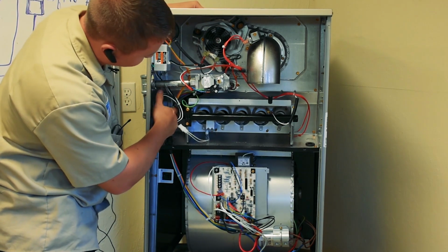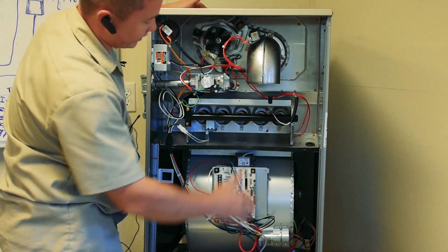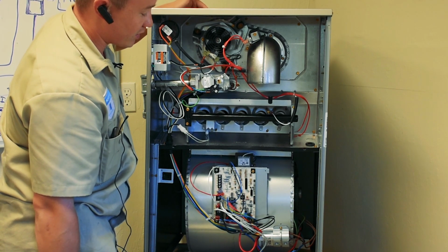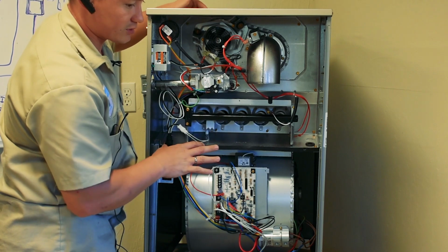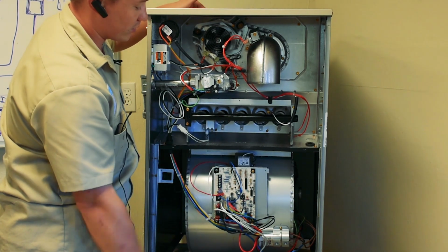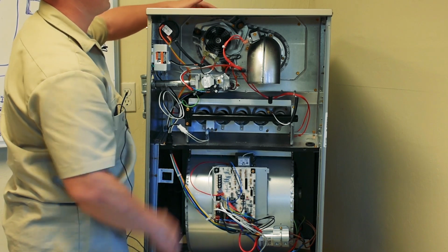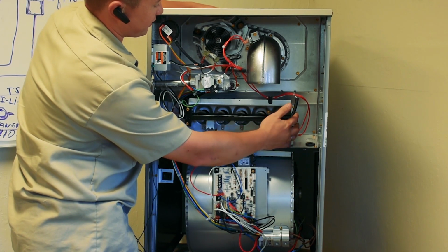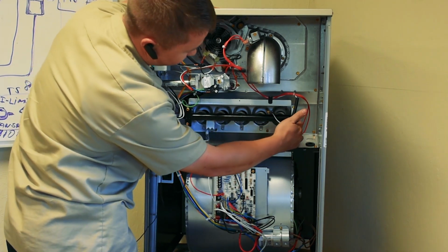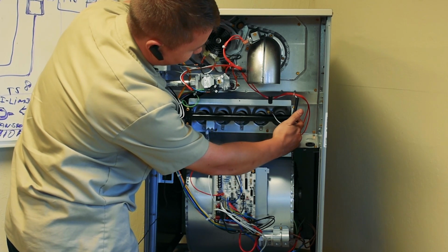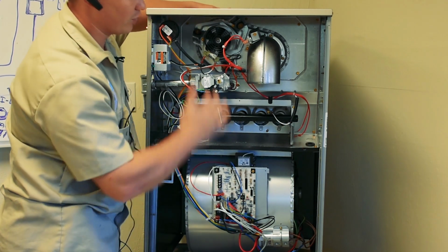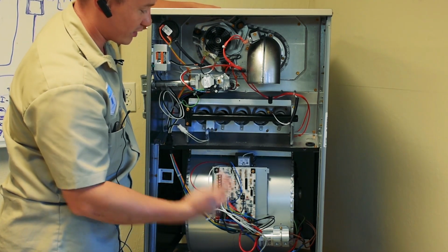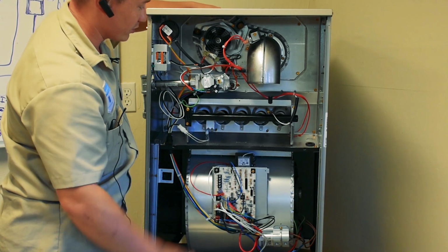This circuit is also connected together with the safety thermostat. On this model it's right here and right here. That thermostat is responsible for protecting the furnace against overheating. When the furnace is running, for example, if your heat exchanger gives too much heat to the frame of the furnace, then this heat will reach these safety thermostats, and they will cut off the whole circuit for running the furnace. It just will not turn on the whole furnace.